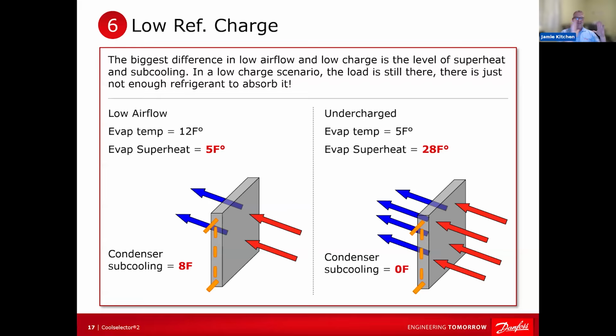So remember, if you're charging a SEER 13 system and you're charging to a given outdoor ambient and wet bulb temperature, and you're used to doing 13 degrees of subcooling, and you go to a SEER 17 system, you ain't charging to 13 degrees of subcool anymore. You're probably charging to 8 or 9, right? And so if you charge it to 13, you just overcharged that system, and they just dropped 2, probably maybe 3 SEER points, right? And they're not going to get the money out of it. So congratulations, right? Make sure there's no rule of thumb to follow here. Make sure you follow those guidelines.